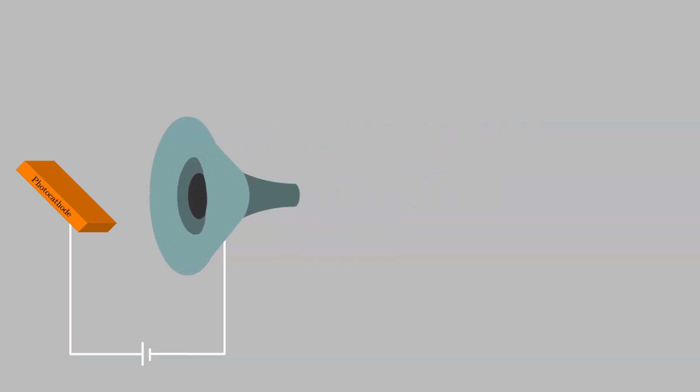Let's build one up, step by step. Firstly, we need a photocathode, carefully chosen and coated for the specific photon frequency we want to measure. We place it right here at the entrance. When a photon ejects an electron from the photocathode, that electron has a random velocity, so we need to focus it. For focusing, we use a process similar to an electron gun. We use a metal focusing electrode that creates an electric field, acting like an invisible funnel. The electrons naturally want to follow this electric field path, so they are perfectly guided towards the next stage.